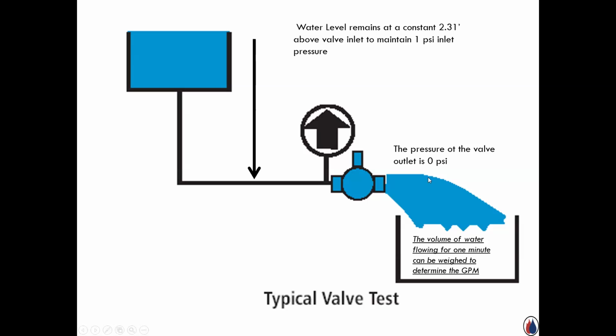So the orifice is smaller to create that 1 pound pressure drop. So if I'm trying to move more GPM through that smaller hole, I'm eating up more energy. If I have a valve that has a higher CV, that means more GPM had to go through that valve to create that 1 pound.